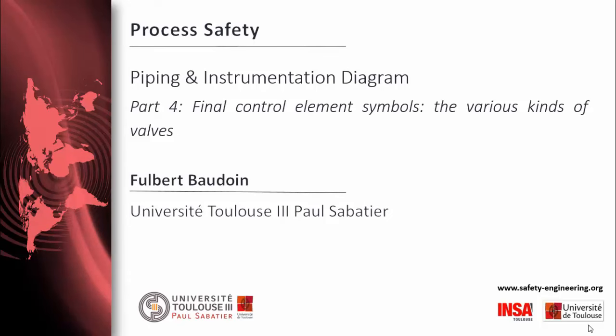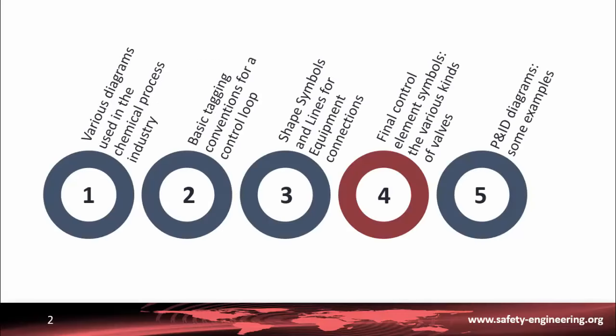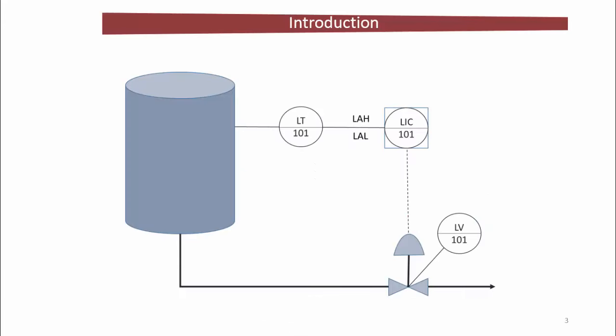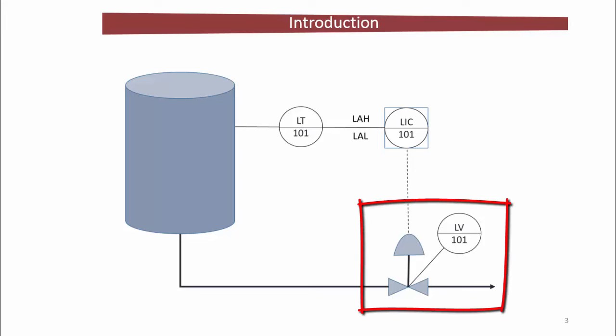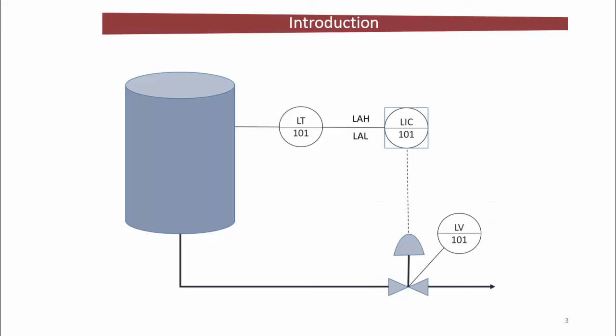Hello, this is Fulbert here. We are going to take a closer look at specific types of valves and their symbols. Let's take another look at this control loop. We have already explained the details and the tagging — for example, LV means the valves that control the level inside the tank. The associated symbols mean that the valve used here is a spring diaphragm valve without a positioner. In this part, we are going to focus on the different kinds of valves in the chemical process industry as well as their symbols and associated devices.